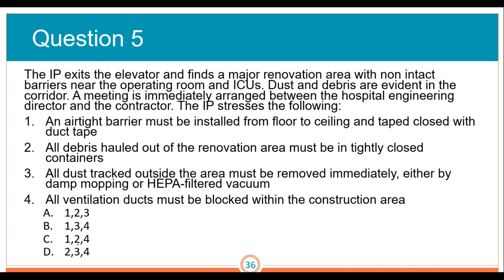Question five: the IP exits the elevator and finds a major renovation area with non-intact barriers near the operating room and ICUs. Dust and debris are evident in the corridor. A meeting is immediately arranged between the hospital engineering director and the contractor. The IP stresses: one, an airtight barrier must be installed from floor to ceiling and taped closed with duct tape; two, all debris hauled out of the renovation area must be in tightly closed containers; three, all dust tracked outside the area must be removed immediately either by damp mopping or HEPA-filtered vacuum; and four, all ventilation ducts must be blocked within the construction area.